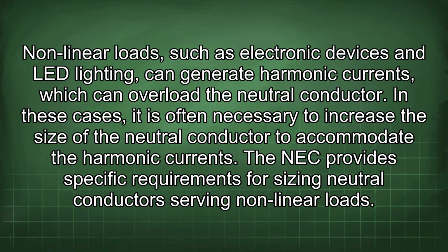Another factor to consider is the type of load being served by the circuit. Nonlinear loads, such as electronic devices and LED lighting, can generate harmonic currents, which can overload the neutral conductor. In these cases, it is often necessary to increase the size of the neutral conductor to accommodate the harmonic current. The NEC provides specific requirements for sizing neutral conductors serving nonlinear loads.